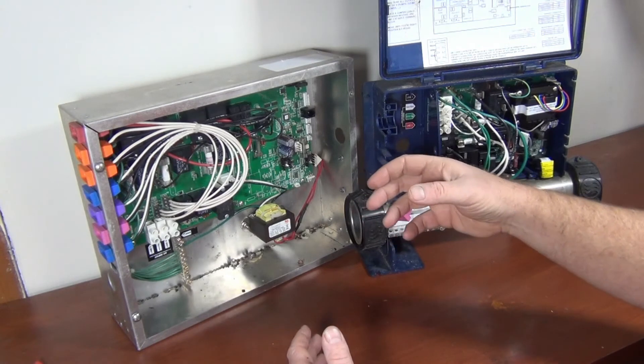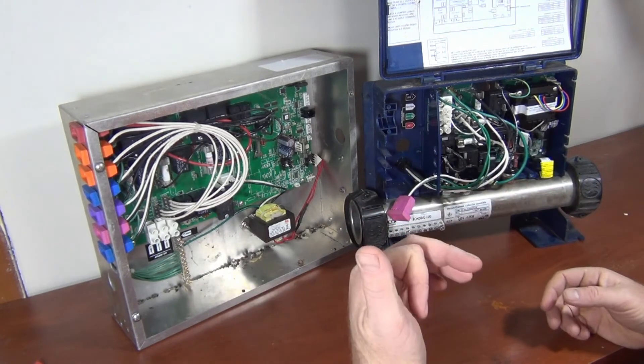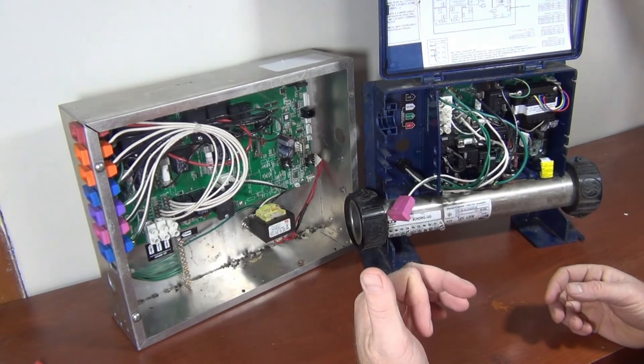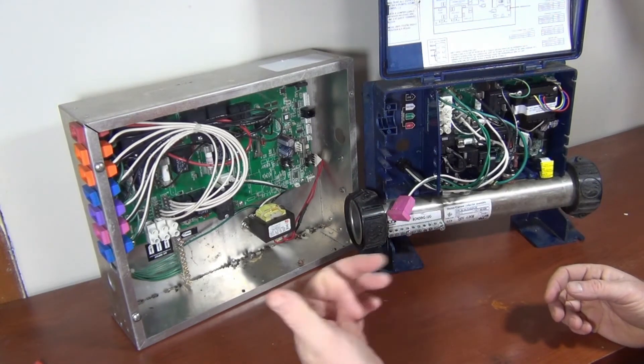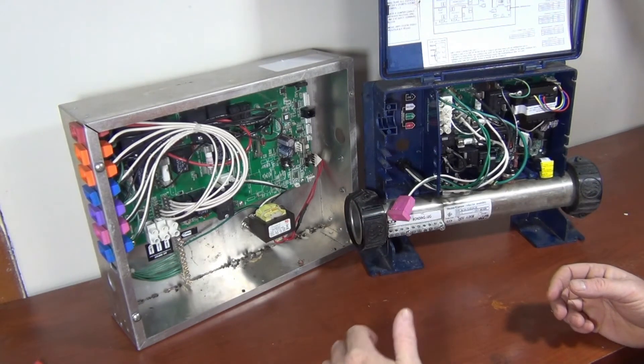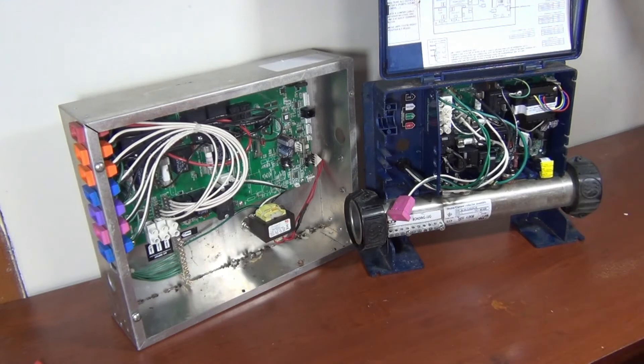So disconnect here. If you disconnect it out, and you go turn the breaker on, and if it trips, it's the breaker.